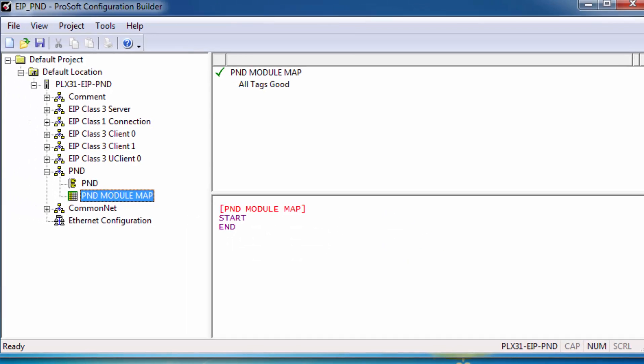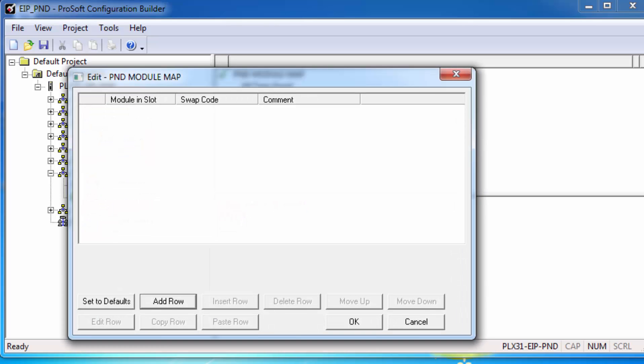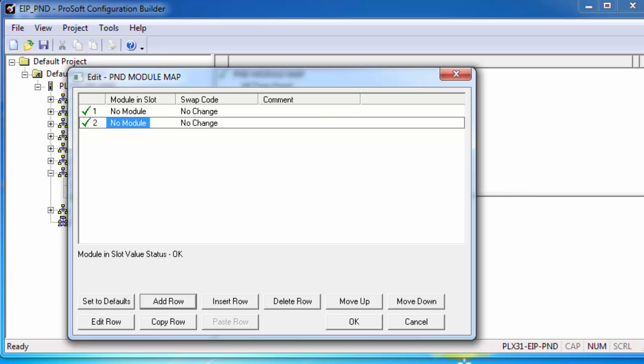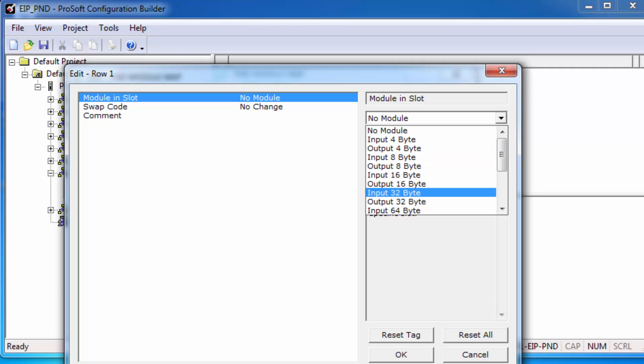Next, click on PND module map. Right-click and choose Configure, Add a row, Edit that row. Here is where we'll host and receive specific amounts of data for the PROFINET controller. Let's say a PROFINET controller needs to send us 32 bytes of data and receive 32 bytes of data.